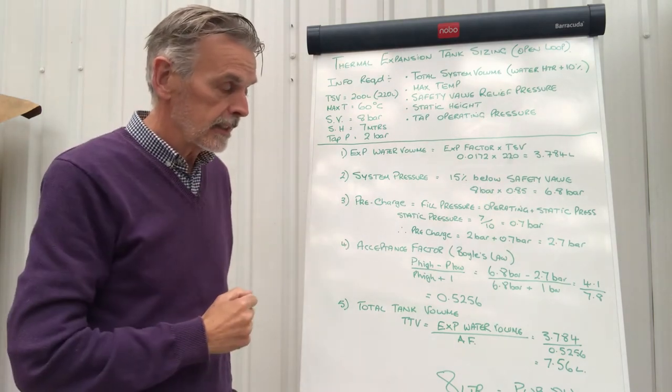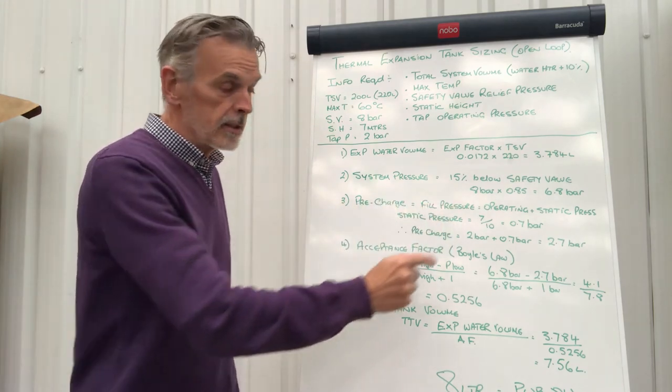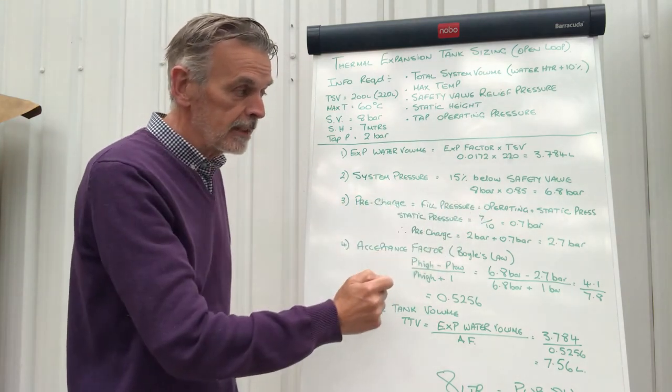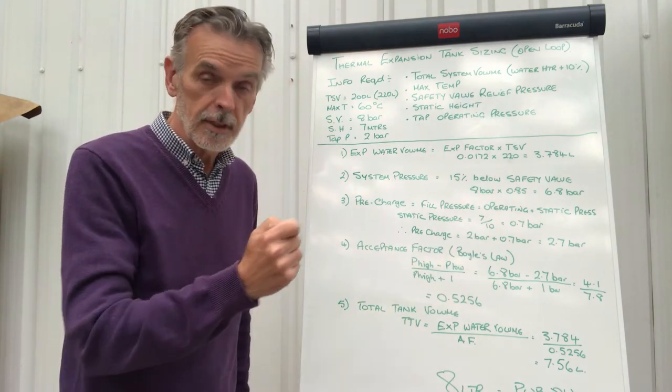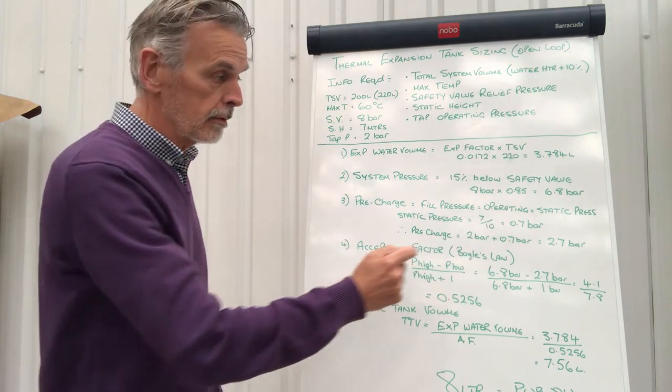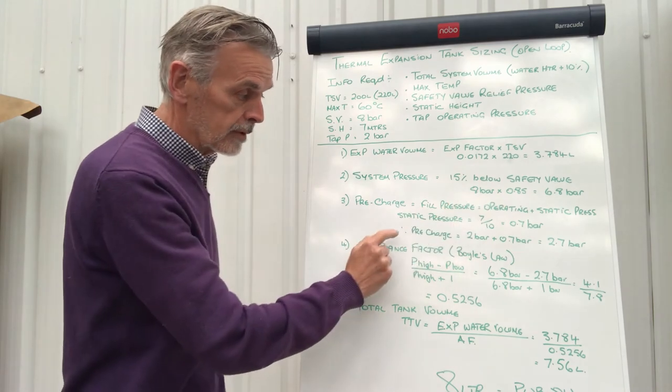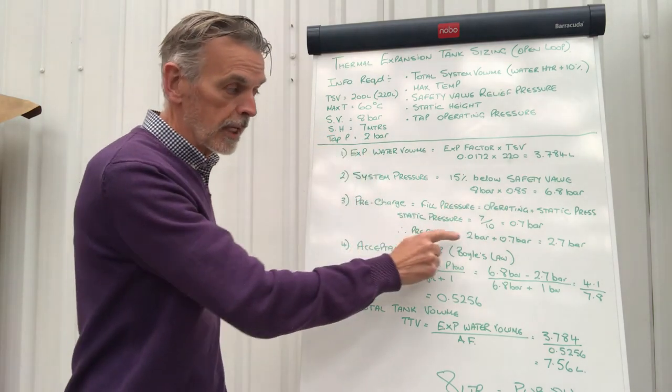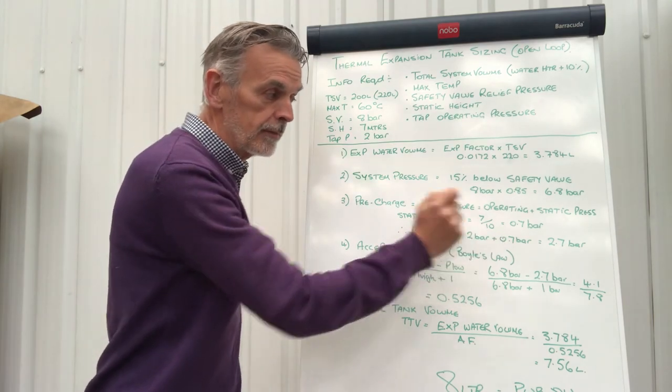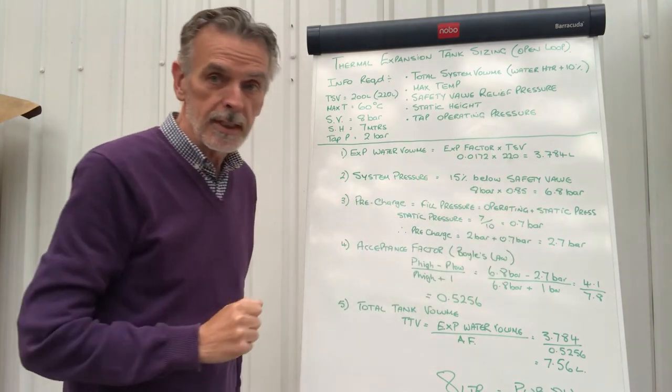So in this particular calculation, that's 7 metres. So 7 metres divided by 10 is 0.7, and that's converted it into bar. So 0.7 bar. So the pre-charge is now the tap pressure you require of 2 bar plus 0.7 bar equals 2.7 bar.